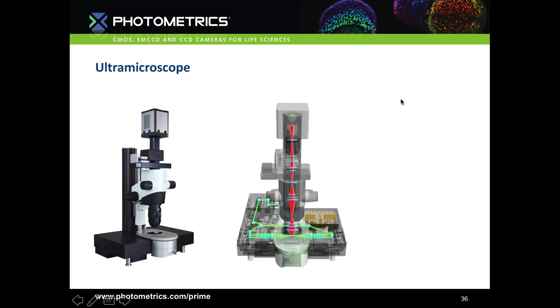The ultramicroscope is typically used for very large and optically cleared samples. The detection objective is a 2x providing cellular resolution, with an 18mm field of view and up to 10mm working distance, making it perfect for larger samples. The lightsheet is formed and split to illuminate the sample from both left and right, and further split into three lightsheets per side. Choosing dual view gives you six lightsheets total, providing fantastic resolution through large optically dense samples.